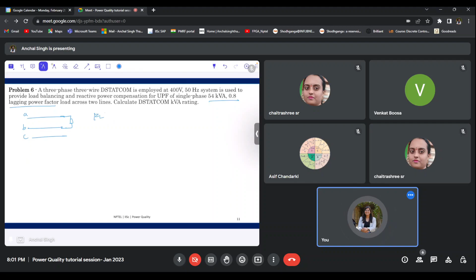So again we have A, B and C, and then there is a load connected here, right? The impedance of the load can be directly found as VAB square by SL, which is 400 square by 54,000, which will be 2.963 ohms. Now we already know the power factor, so we can calculate ZL as 2.963 angle 36.87 degrees.